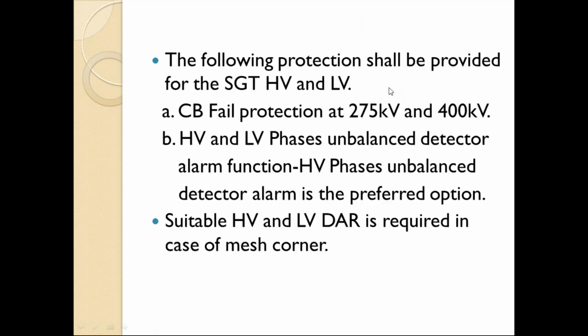So this is one type of protections. The following shall be provided for SGT, HV and LV. Normally SGT is 275 kV, and it is a CB fail protection they will be giving, and also LV phase unbalanced detector alarm, and it is also suitable for HV and LV DAR, which is required in case of mesh corner protection.